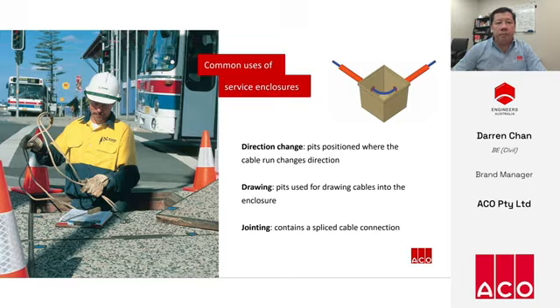Here are the main functions for cable enclosures. Pits are used when a cable run needs to change direction. The cable exits before and re-enters the conduit after the bend. Conduits can be installed on gentle bends, but for sharp bends, a cable pit is required. Also known as pulling boxes, pits can be used for drawing or hauling cables. Cables can be looped and heaped into one enclosure and then fed into the conduit to be pulled to the next enclosure. Jointing pits, also called splice boxes, are for enclosing a spliced cable connection. These cable pits must be correctly sized to accommodate the cables running through it as well as the size of the connector.